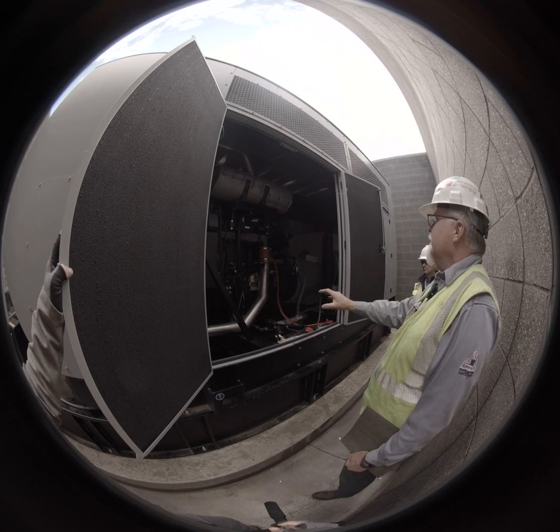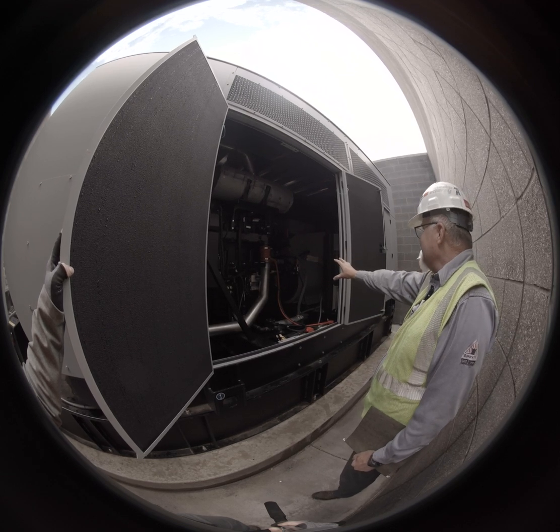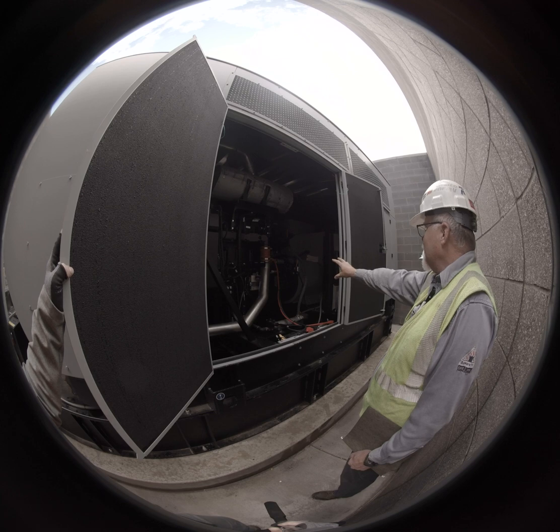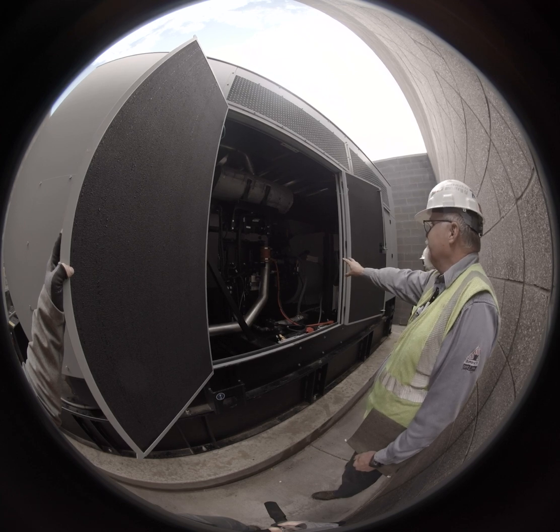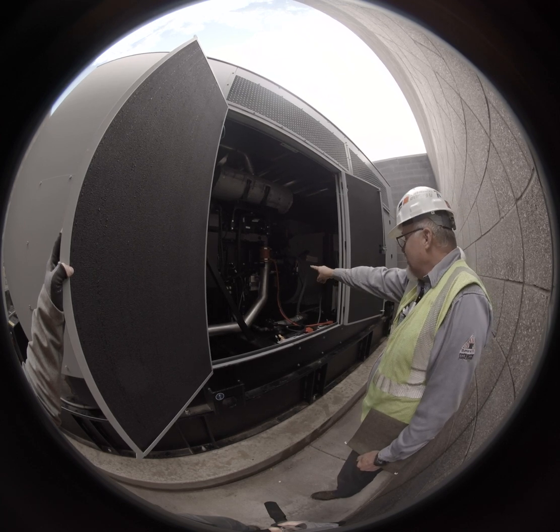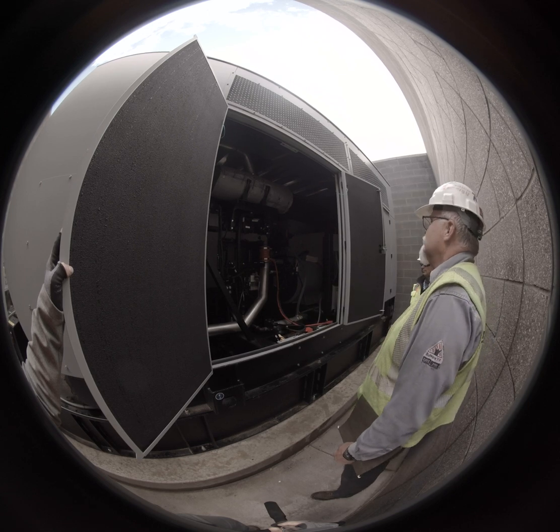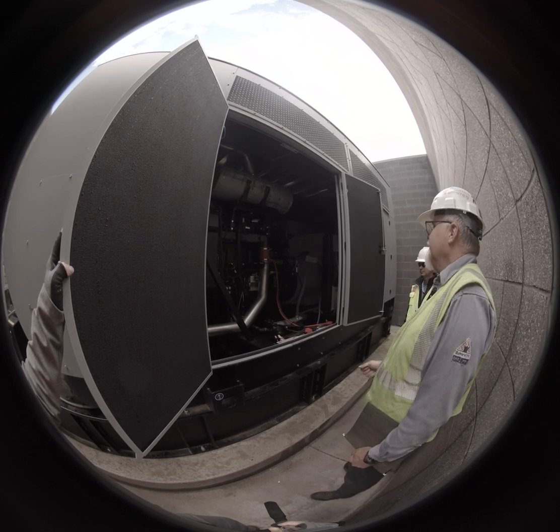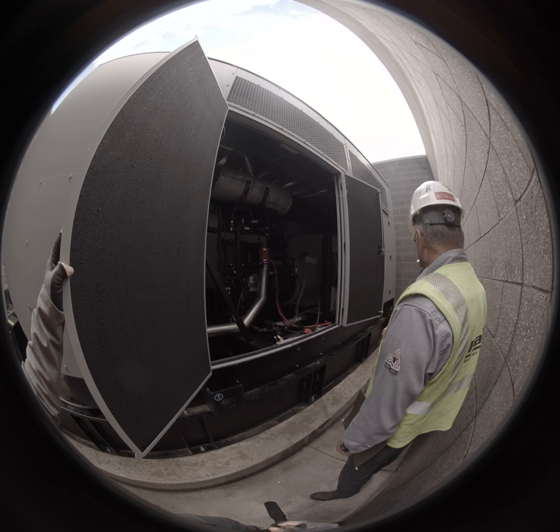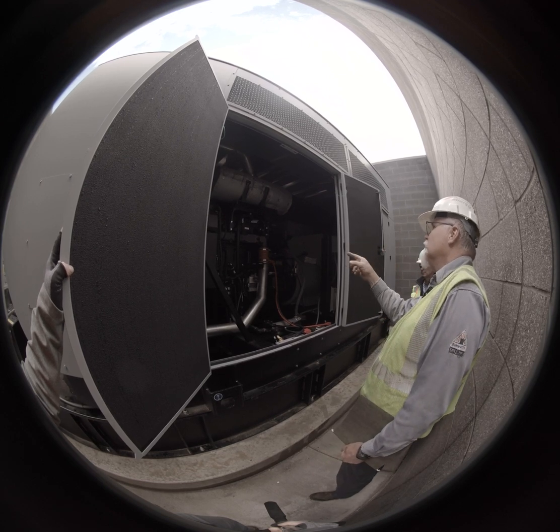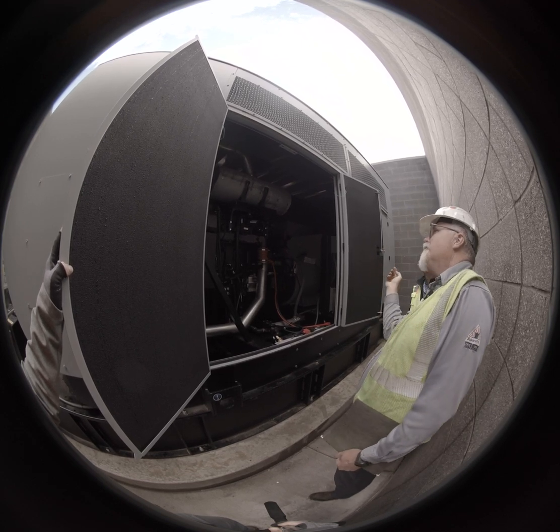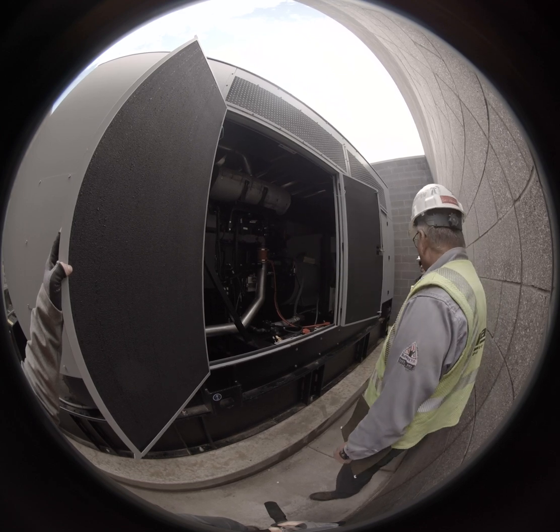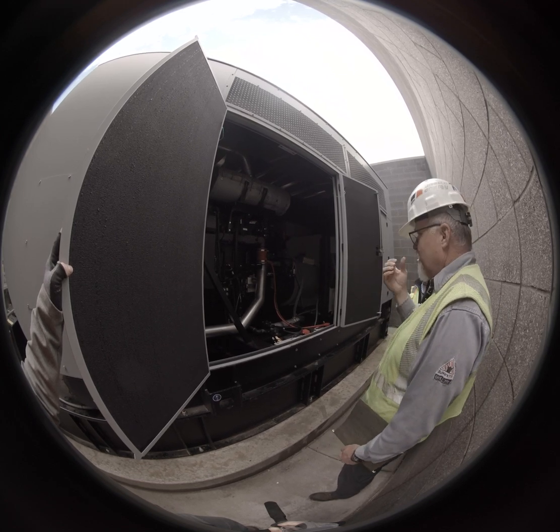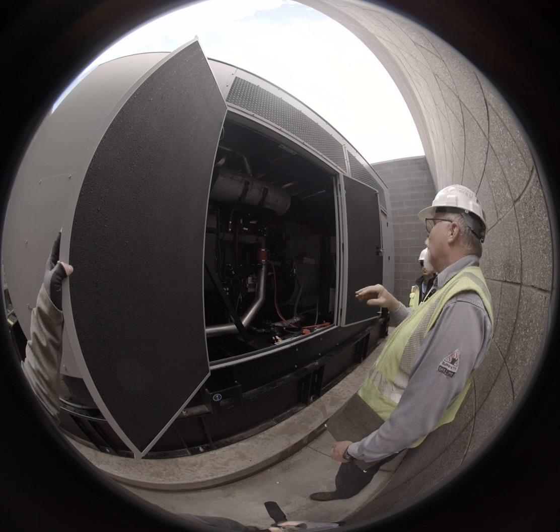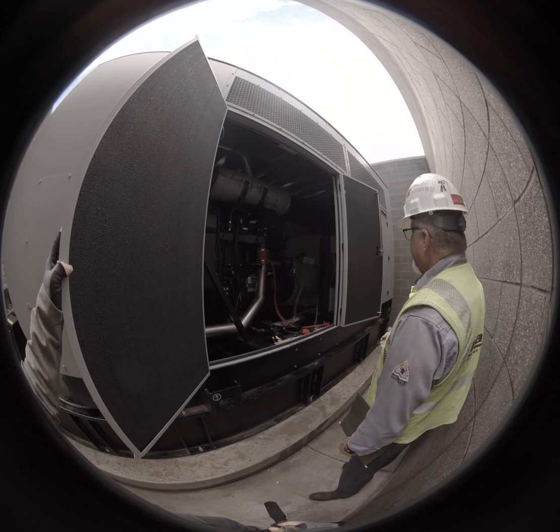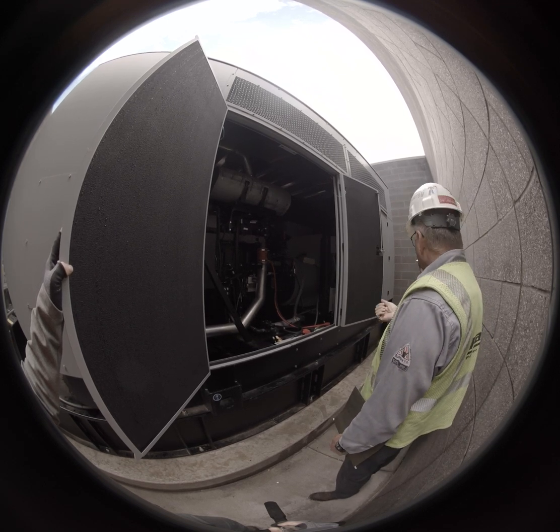This side of this engine, you have our starting system, 24-volt starter with control relay sitting right behind it. This big silver pipe here is part of your charge air cooler. So basically, when you compress air, you create temperature. And out of the turbocharger, which we'll see on the other side, it pushes that up through a second radiator core, an air-to-air exchanger, to cool it down before it puts it back in the engine. Because the cooler you can keep the air, the more oxygen you get into it, the more horsepower you can get.